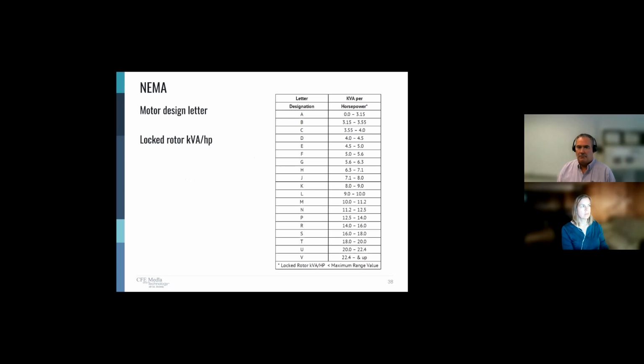Now we can talk about the design letter. And this refers to the locked rotor energy per horsepower. Okay. And this is a range value. So if we have more locked rotor energy per horsepower, then we're going to be a high letter versus a low letter. This is important for us to know as we're designing, if we're designing an application where we're actually specifying the motor tied to the piece of equipment and we know the characteristics of the piece of equipment, we may have to modify our motor locked rotor starting conditions. This number would be important.